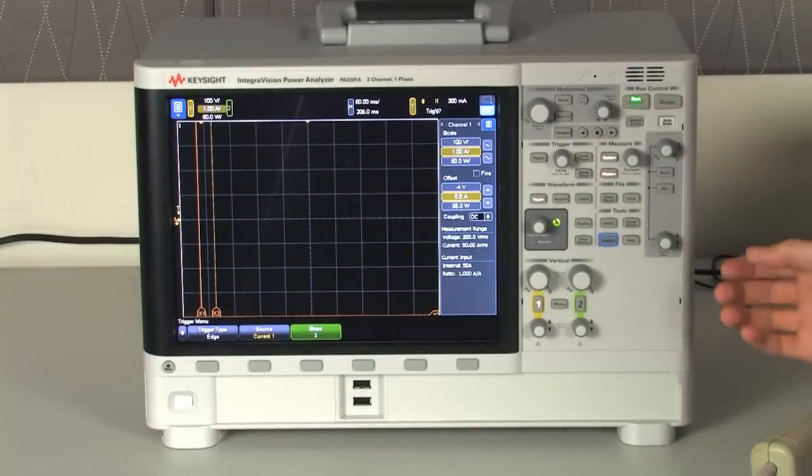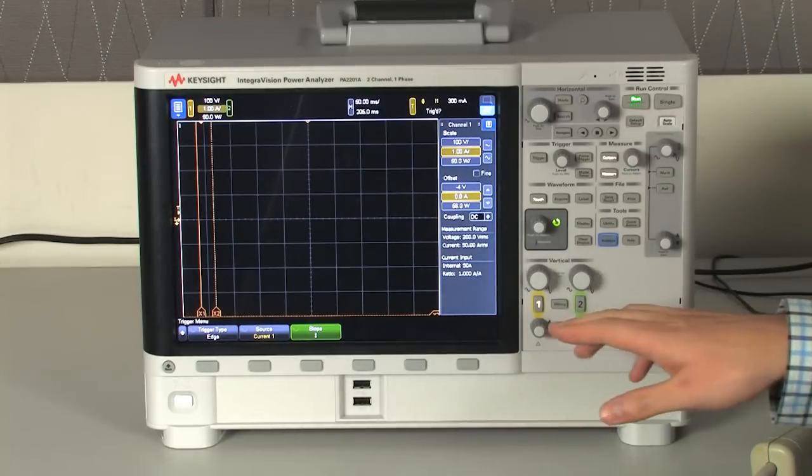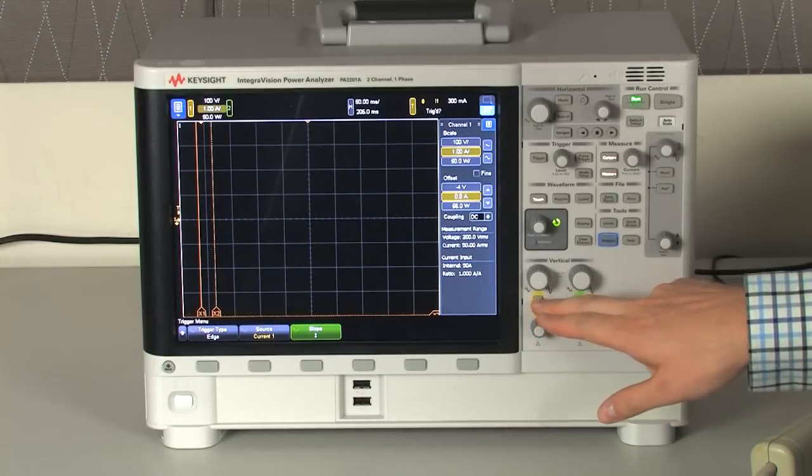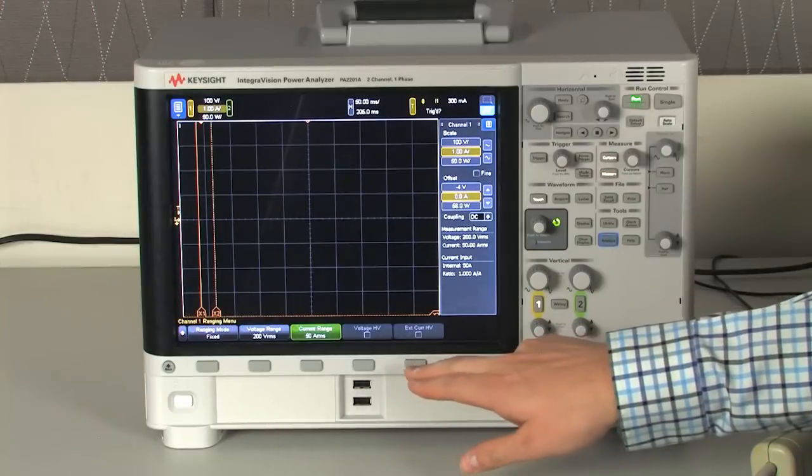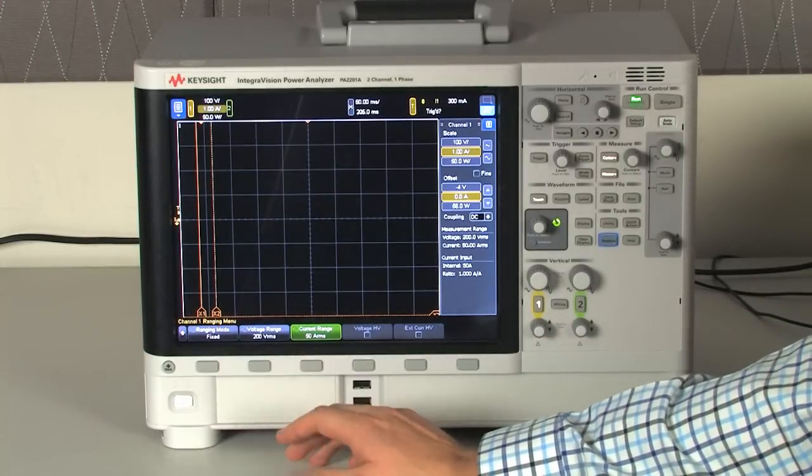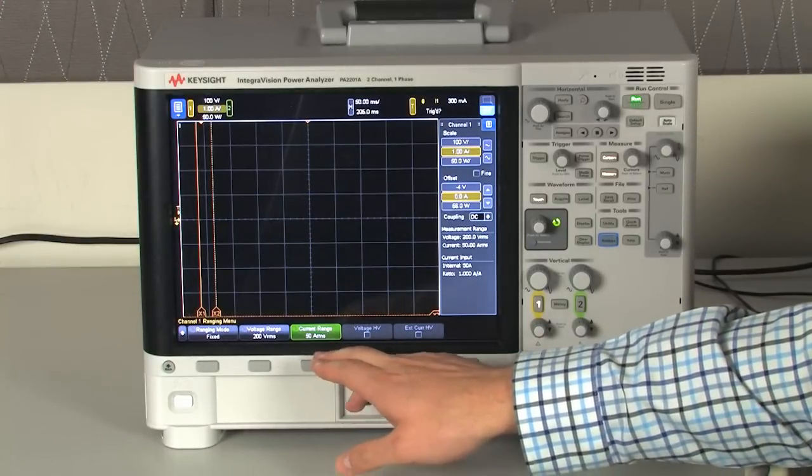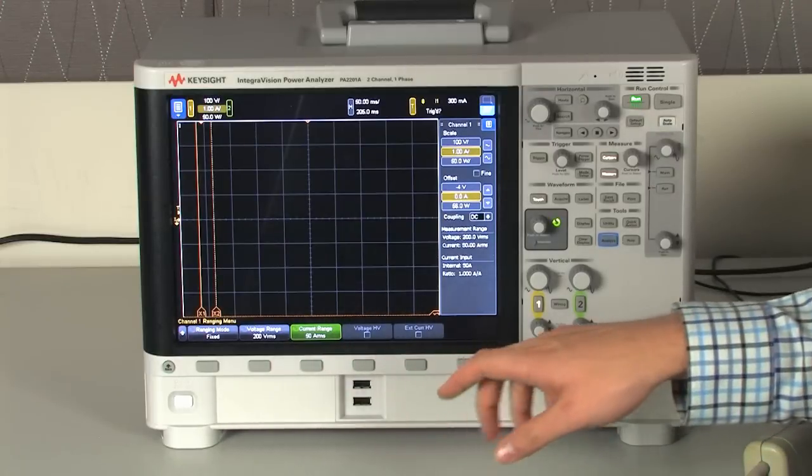Another unique feature about the IntegraVision Power Analyzer is its ability to measure transient events. We have a DC switching power supply hooked up to IntegraVision Power Analyzer. And now we're going to try to capture its inrush current. So I've already set the display to be just displaying current. Now I'm going to go into the channel 1 menu and set the ranging to fixed. This is important so we can capture the full peak of the inrush current. So I set the inrush to 50 amps and the voltage range to 200 volts.